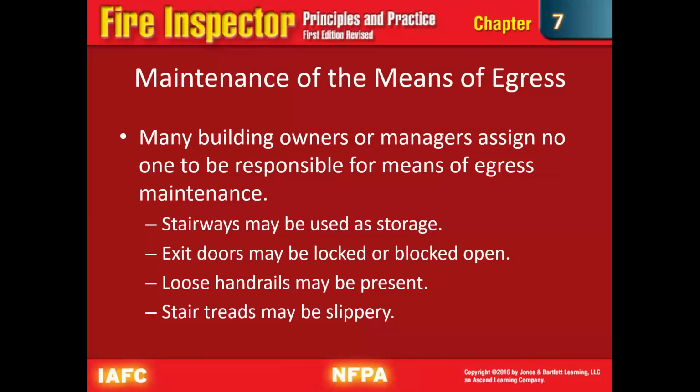Your maintenance of your means of egress. Many building owners or managers don't assign anybody to be responsible for the means of egress. Stairways may be used as storage. The exit doors may be blocked from the outside, blocked from the inside. I've seen where places wanted to store combustibles right next to the egress door.